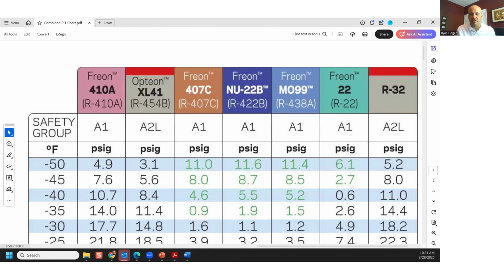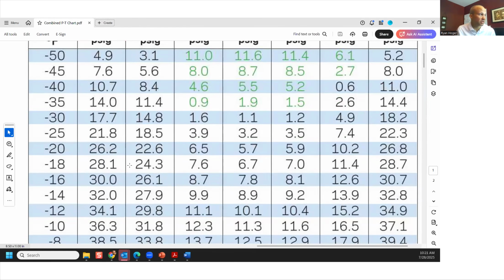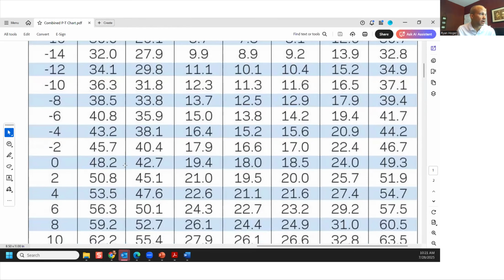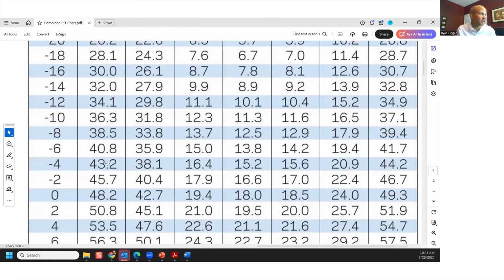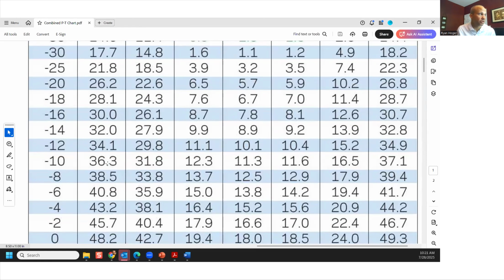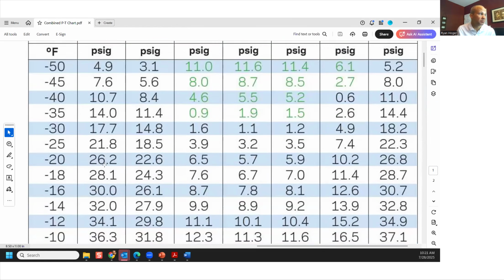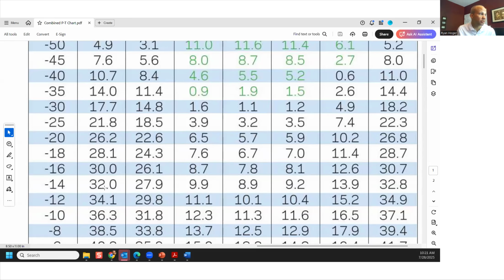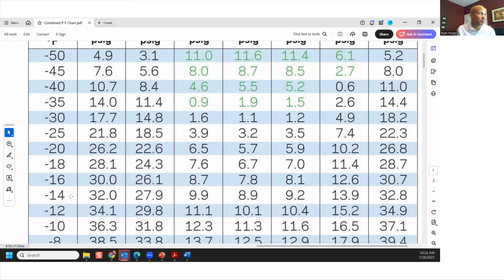Do me a favor, type something in the question chat box for an R410A temperature that you want to compare it to, or pressure. I don't care either way. Just throw something in there so we've got something to debate about, or at least look at. While you guys are typing something in, hopefully you are, I'm going to pick a very common one. For some reason, everyone always yells out 32 degrees. I don't know why that happens, because 32 degrees is not a refrigerant temperature you normally would have. But if you were, here'd be your pressure: negative 14, 28 for 454B, 33 for R32.